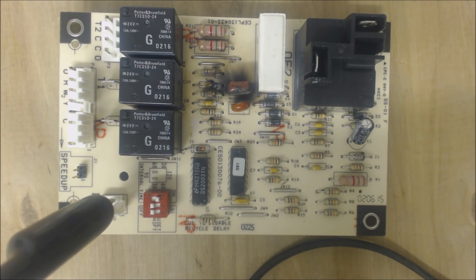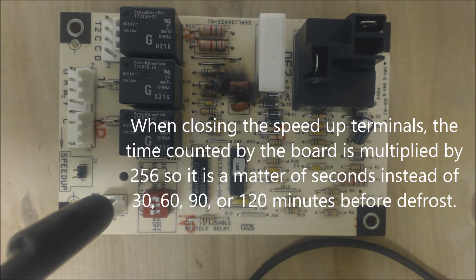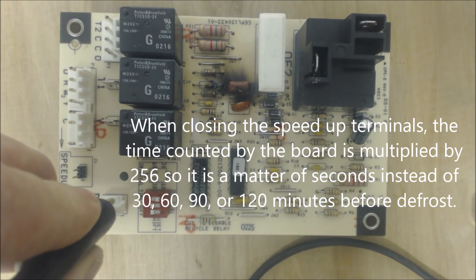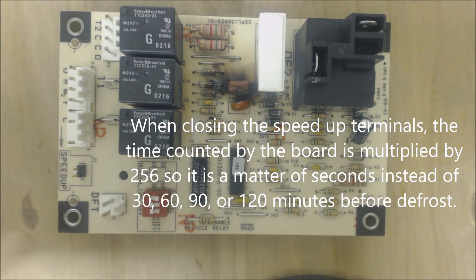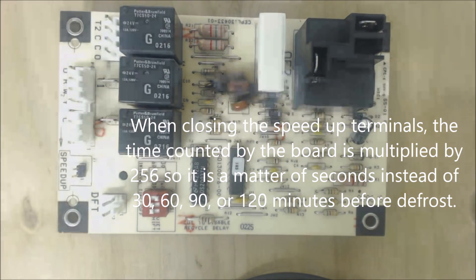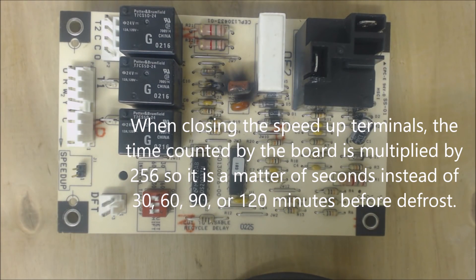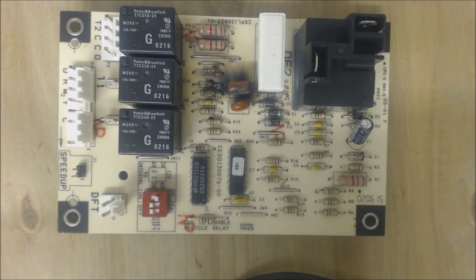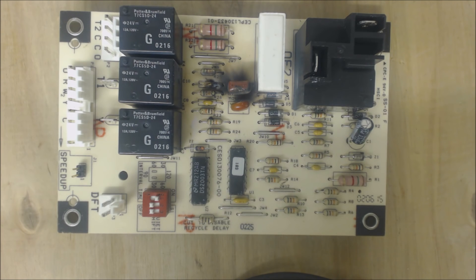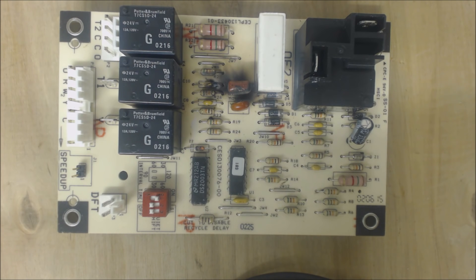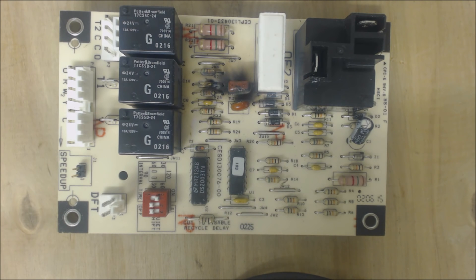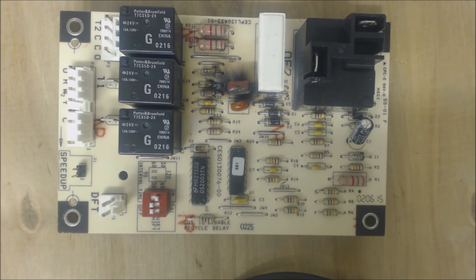And then you enter defrost, where you can check your pressures and temperatures. After that, after you're all done, then what you do to finish up the defrost is you are then reopening the DFT terminals. Now that DFT, what's happening is the defrost will end when the DFT temperature sensor opens at about 65 degrees, 65 to 70 degrees. Once it sees that, it knows that the coil is all melted off. So that DFT sensor is actually on the outdoor fins. And once it gets to 65, 70 degrees, it will open back up again. That will end defrost.